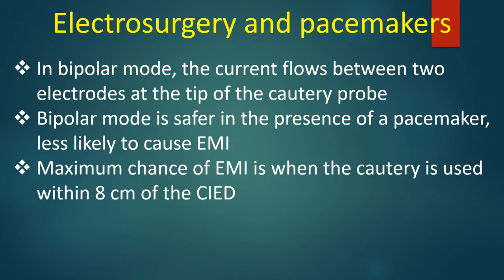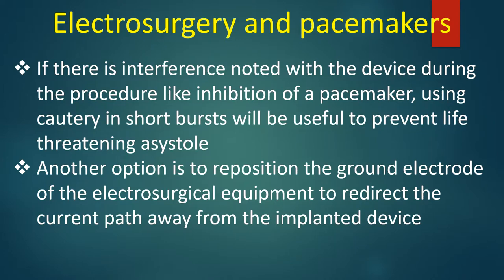Maximum chance of EMI is when the cautery is used within 8 cm of the CIED. If interference is noted with the device during the procedure, like inhibition of a pacemaker, using cautery in short bursts will be useful to prevent life-threatening asystole. Another option is to reposition the ground electrode of the electrosurgical equipment to redirect the current path away from the implanted device.